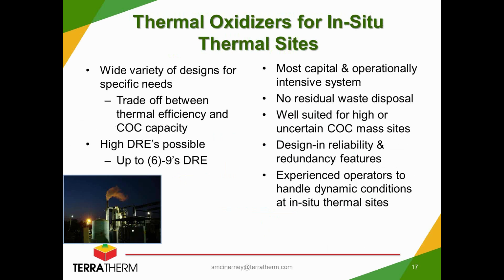So shifting over now to oxidizers, really there's pretty robust equipment, better suited for higher loadings for sure. In terms of the contaminant mass at a site, you get a lot of flexibility to select the equipment and dial in the destruction and removal efficiencies you're looking for. And the key parameters there are what is the residence time in the oxidation chamber, and what is the operating temperature at that residence time.